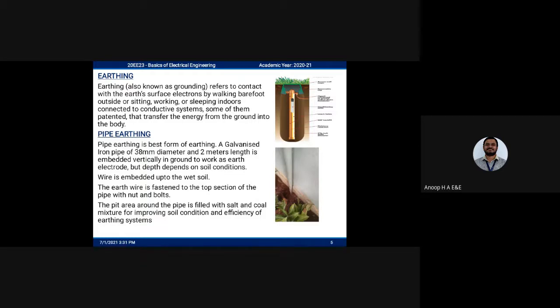Pipe earthing is the best form of earthing. A galvanized iron pipe of 38 millimeter diameter and 2 meter length is embedded vertically in the ground to work as an earth electrode, but the depth depends upon the soil content. The wire is embedded up to the wet soil, and the earth wire is fastened to the top section of the pipe with a nut and bolt. The area around the pipe is filled with a salt and coal mixture to improve the soil condition and efficiency of the earthing system.